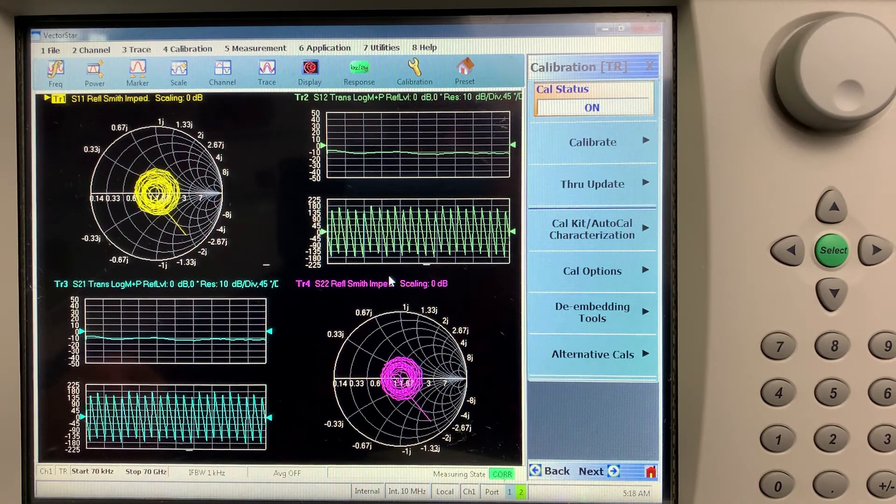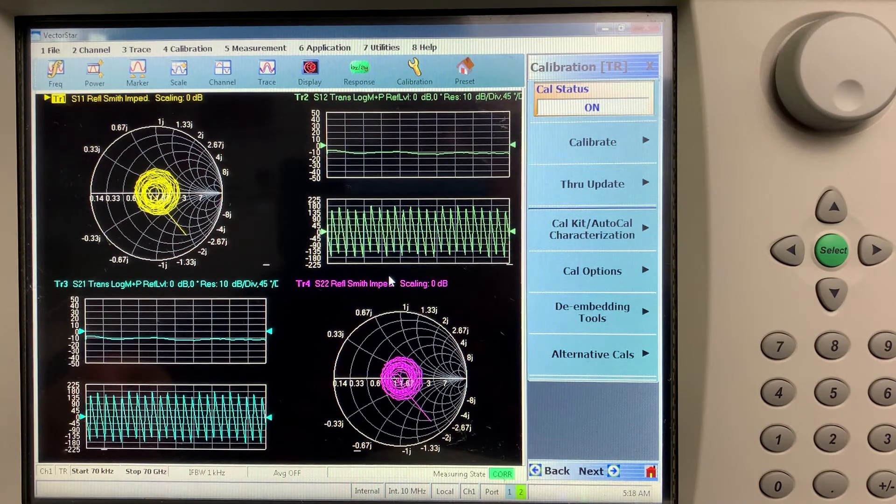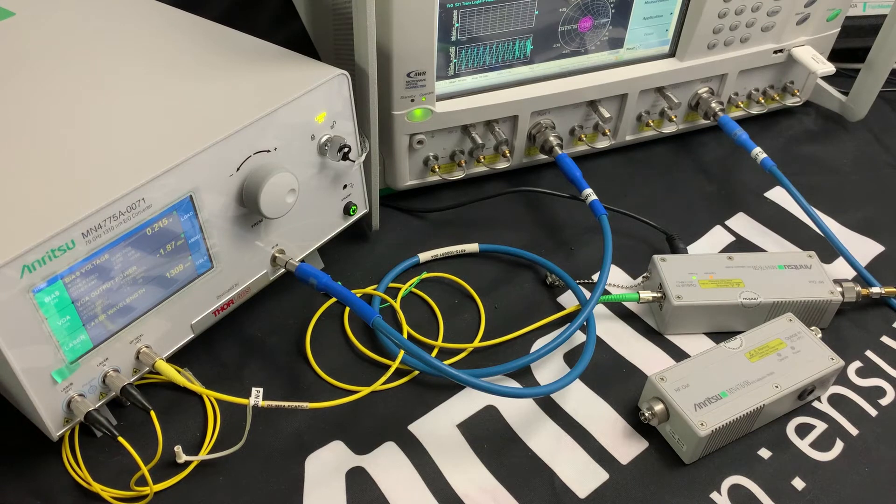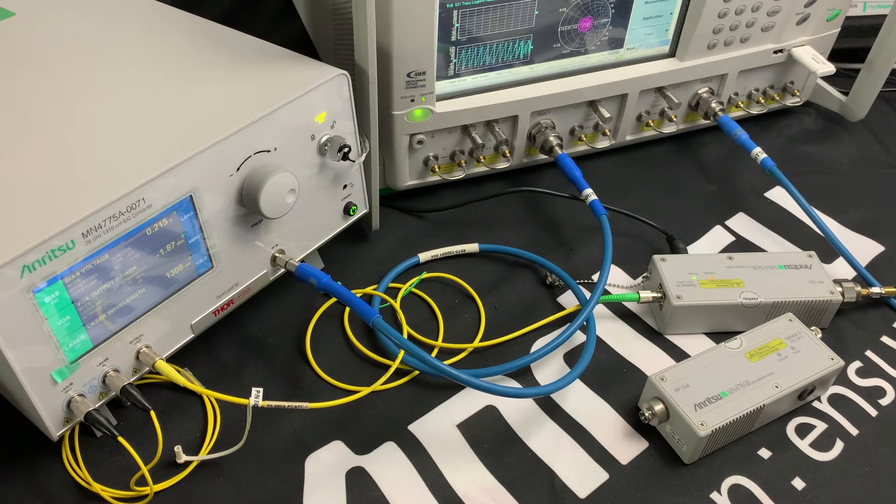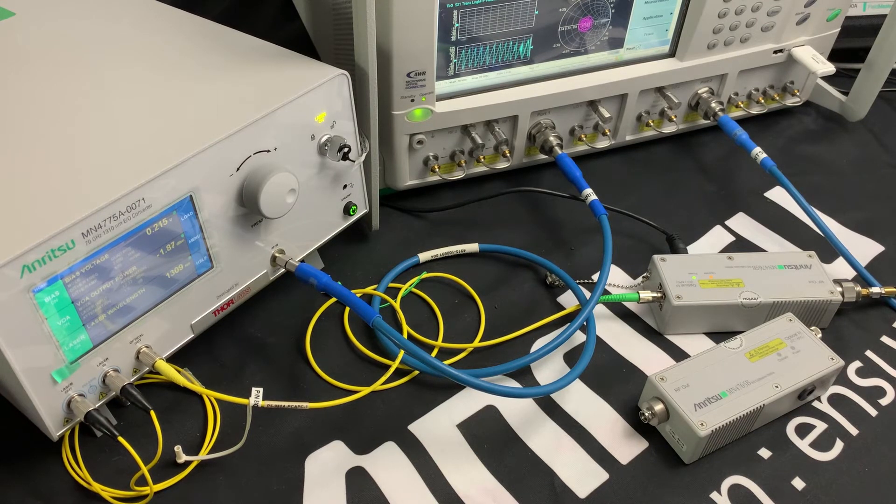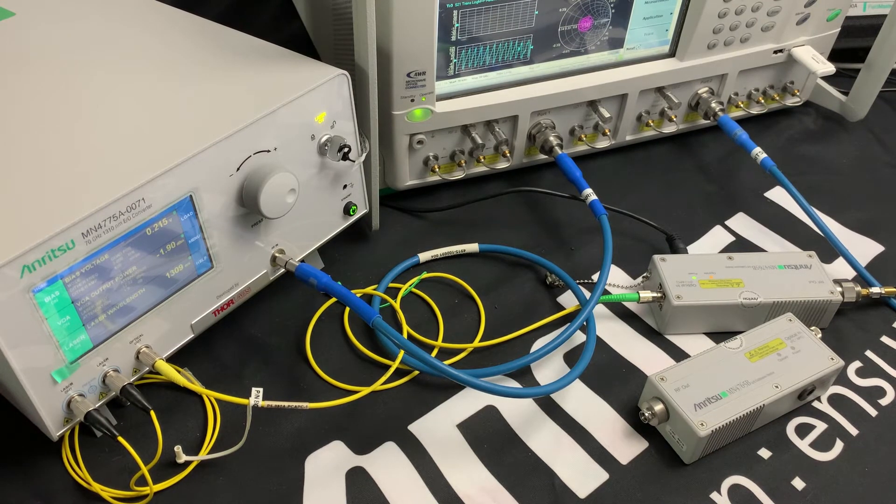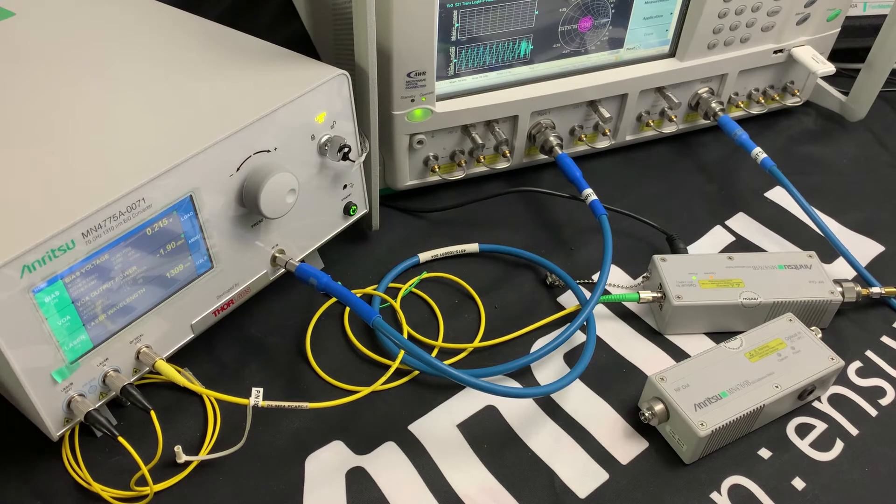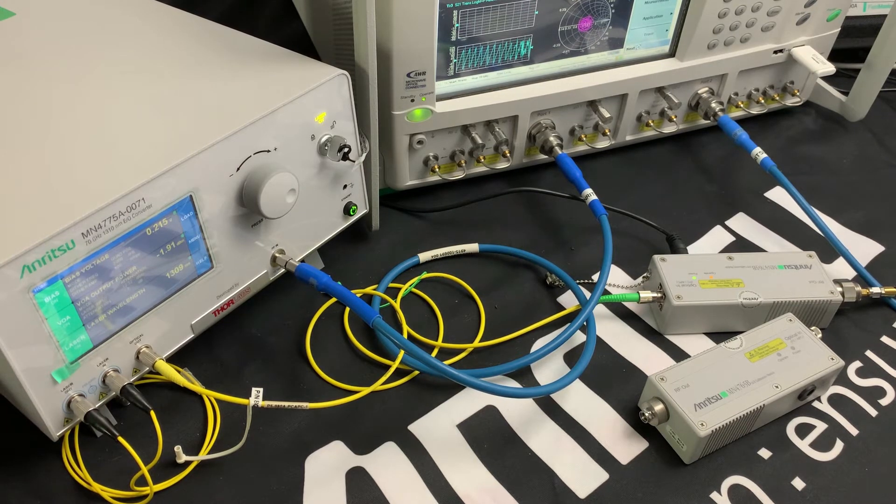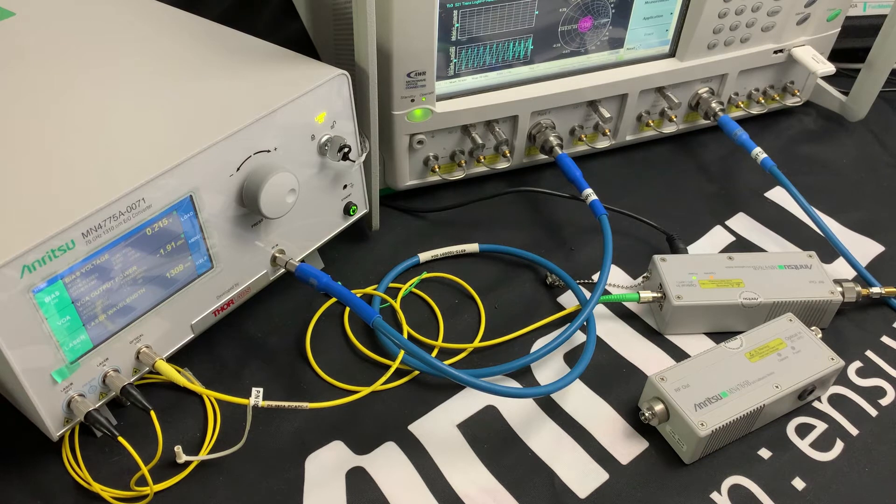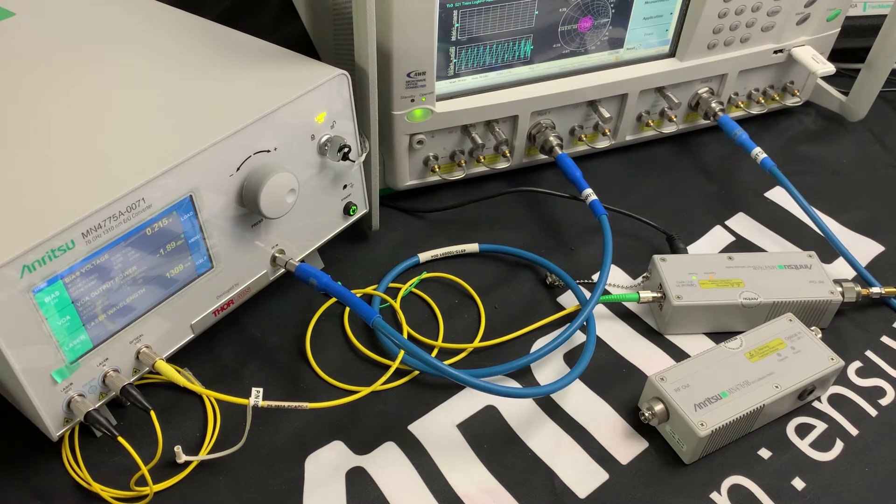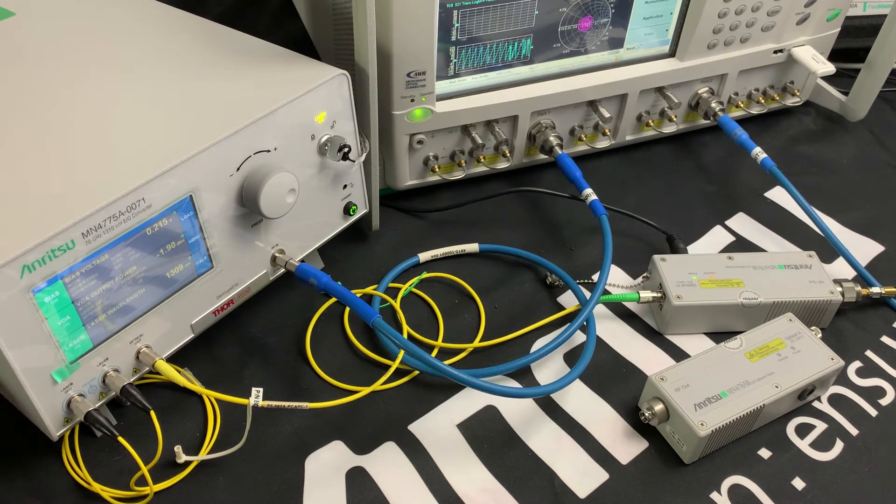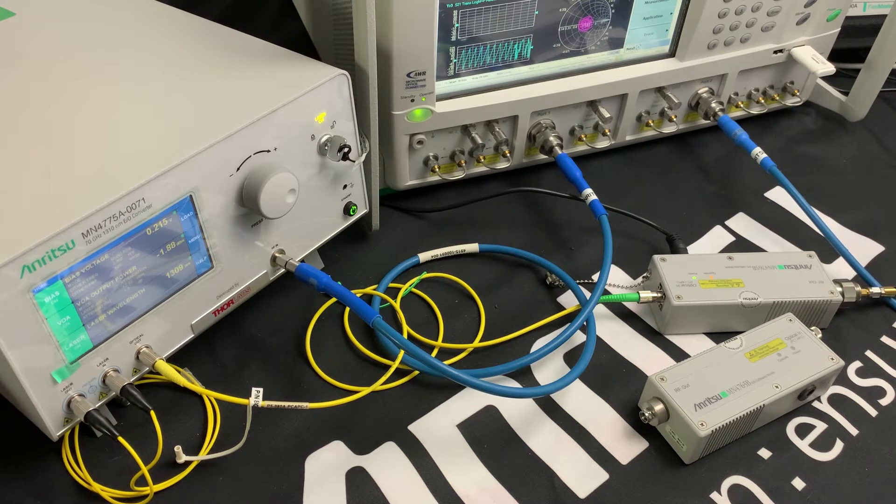So now we can connect our equipment up. I've got port one connected to the RF in of the MN4775A E2O converter. I've got port two of the VNA connected to the RF out of the O2E calibration module. And I have an optical cable between the optical in of the calibration module and the optical out of the MN4775A.